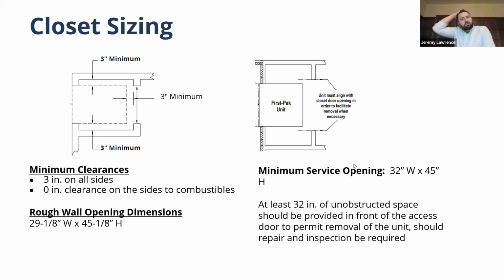So closet spacing, there's 2 ways to install these units. What we call a rear install and a side install. Rear means that the unit slides straight into the sleeve. Side install is if the closet door is in the side and the unit has to get pushed up onto the sleeve, turned, and then pushed in to seal against the sleeve. The rear install is certainly more common. It also makes it easier to work on, and it makes the closet much smaller. In the rear install, you only need 3 inches around this unit for it to operate. For the First-Pak units, which is the high efficiency gas units, a little bit more space, but again, we're trying to minimize the closet space required as much as possible.